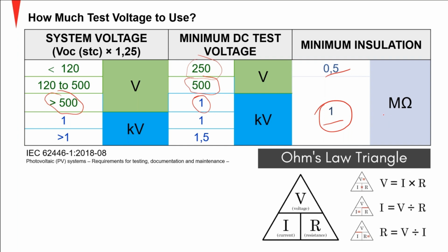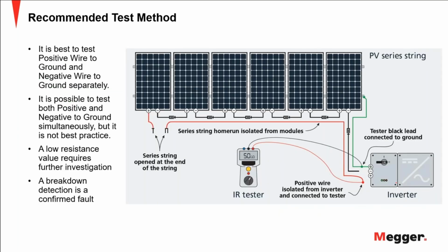It depends on how you are connecting. So there are many factors that can influence the result. But in any case, it should never be less than 1 mega ohm. Around 1 mega ohm, you would like to do some troubleshooting and check connections, check the contamination level of the surfaces, just to be sure you don't have surface leakage. But other than that, that should be a good result.